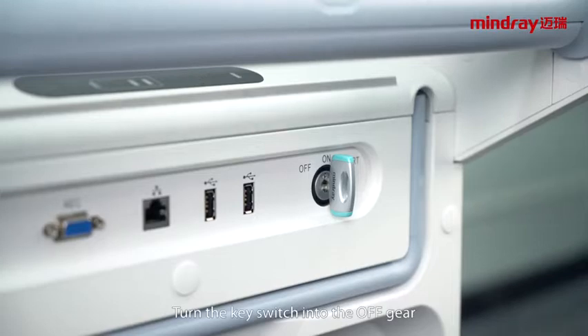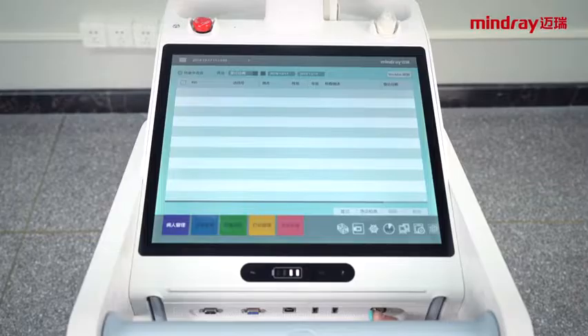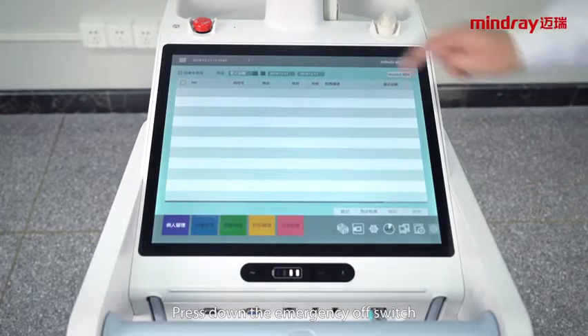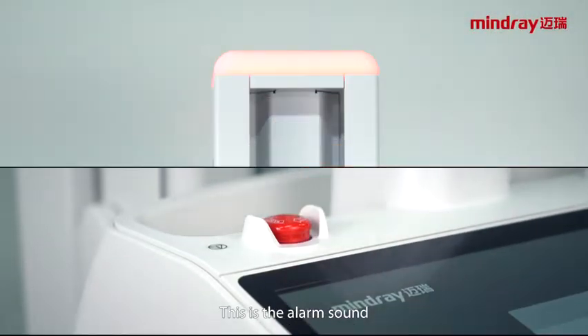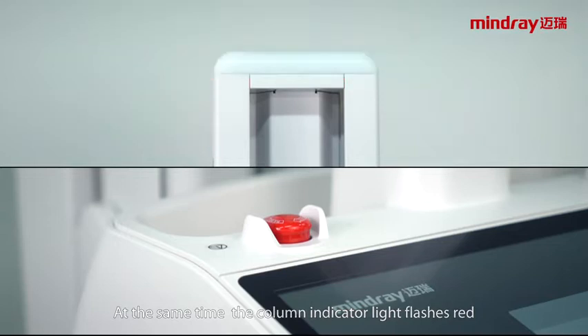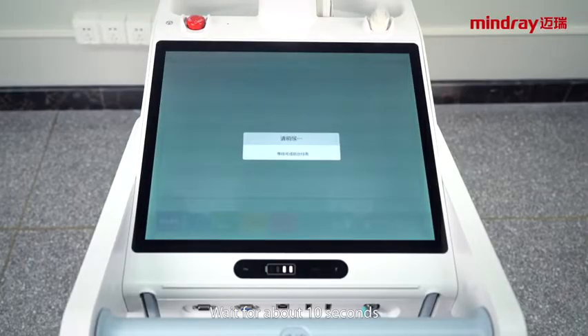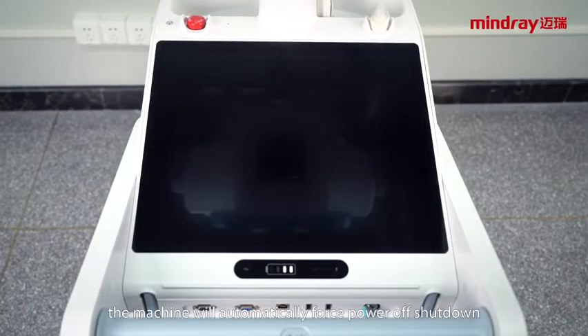Turn the key switch into the off gear. Press down the emergency off switch. This is the alarm sound. At the same time, the column indicator light flashes red. This is a normal phenomenon and don't worry about it. Wait for about 10 seconds. The machine will automatically force power off shutdown.